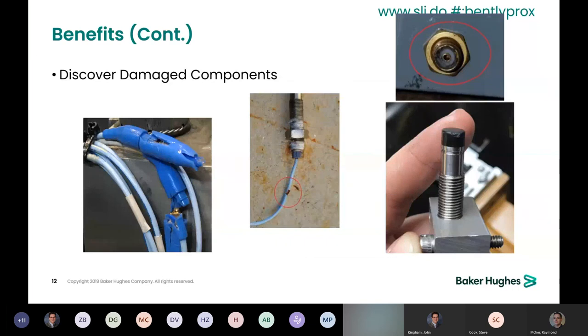Visual inspection of the transducer system can reveal obviously damaged components at times. On the other hand, there are many types of component damage that cannot be revealed during a visual-only inspection. Some damage can only be discovered by electrical verification of the system. In addition, some damage may only be superficial and not result in a loss of performance. The electrical verification will indicate that this is the case.